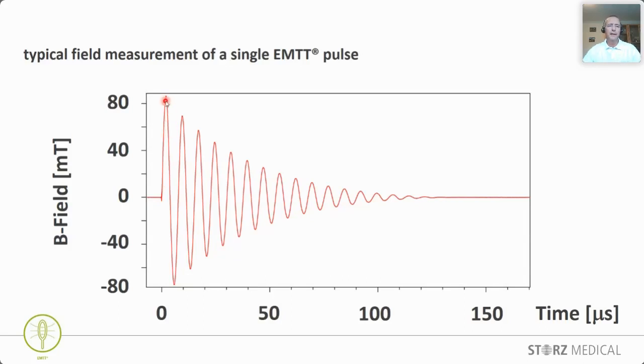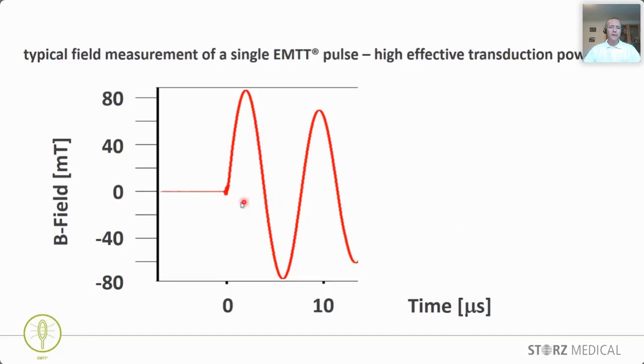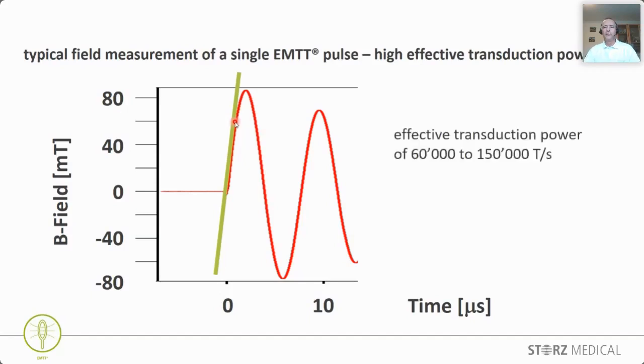Oscillating, it goes up to 80 millitesla, then it starts with this kind of decay curve. Within about 120 microseconds, so pretty fast, the pulse is over. In the meantime, you have seen 15 to 18 of these oscillations going up and down. Very important for us is this central part in the beginning. Let's zoom into this, what I circled in green, and look into this one. Here you see, as soon as the charge is going over the coil and back and forth and starts oscillating, there is a very steep curve where it's going up. This steep curve, as I indicated in green, we call the effective transduction power. Here, this has a value of up to 60,000 tesla per second, and it can be up to 150,000 tesla per second. It depends, as it's decaying, it's coming down from the big value a little bit.